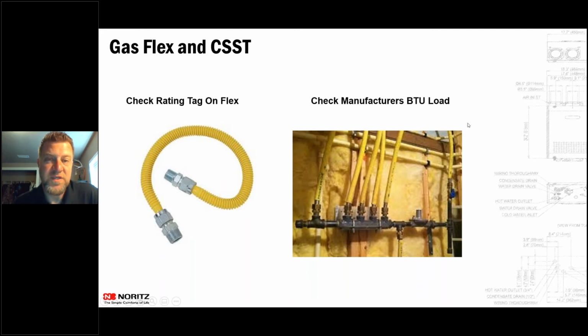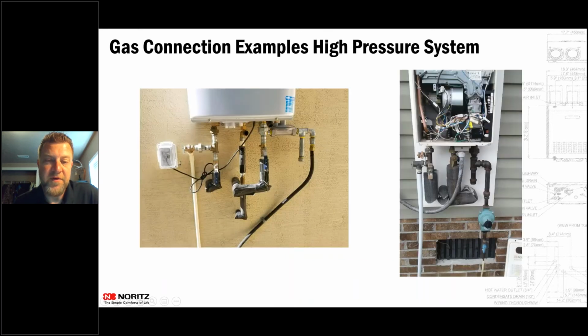So I mean, the biggest issue we see with tankless water heaters is they're not sizing the gas lines correctly. So kind of a couple examples with this unit here. They've got that reg right there on the gas line. It's 2 inches away. They were getting 11 codes, which is an ignition code, because it had too much pressure going into it. Same thing with this setup right here. That reg is a little too close to that unit. We would like to see that at least 3 feet away.